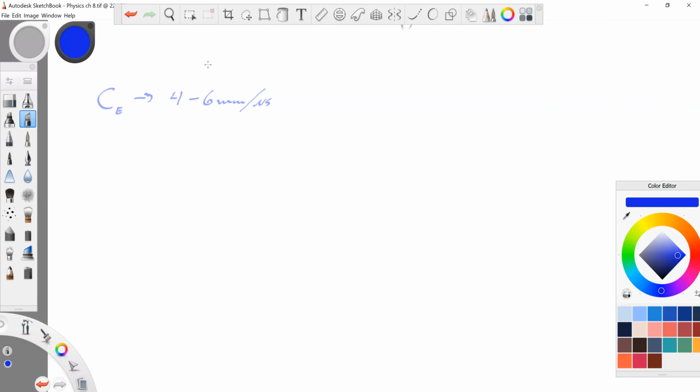So, mathematically, let's just jump to page 125. We need to look at this mathematically, and then I can give you an illustration of what's going on. How does this thickness of piezoelectric material, lead zirconate titanate crystal, affect frequency? So the thickness, PZT thickness, and frequency are inversely related. Thinner active elements create pulses with higher frequencies.